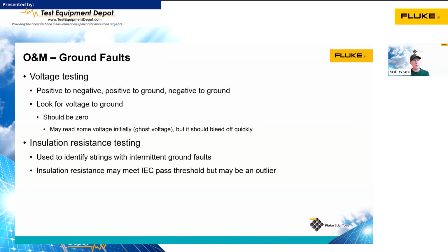So it's not going to tell us where the ground fault is exactly located, but it's going to tell us at least what string has the ground fault. And we may be testing and we may see insulation resistance that's above what the standard we're using says, but maybe it's lower than what we expect, or it's lower than other things that are similar in the system. That would be a cause for concern and something that's an outlier, and we want to investigate further.